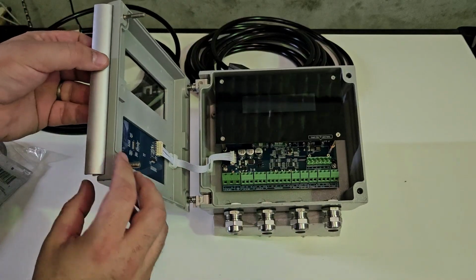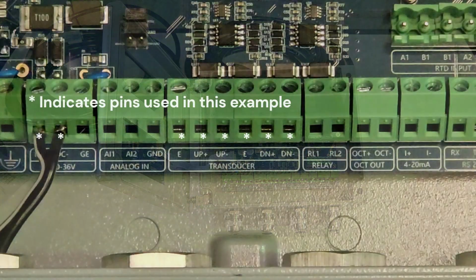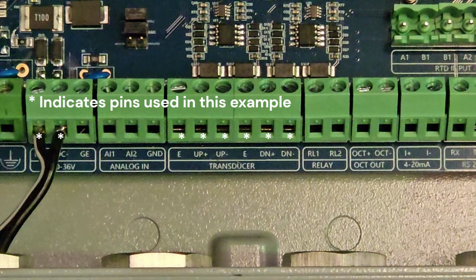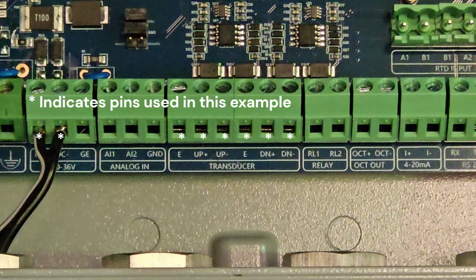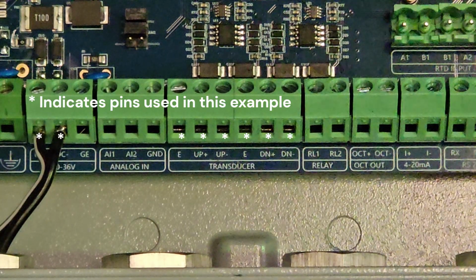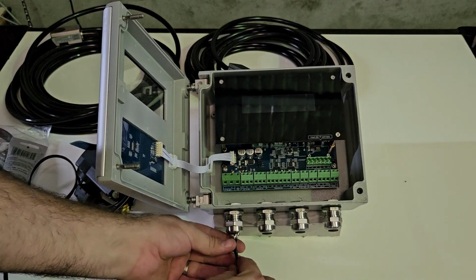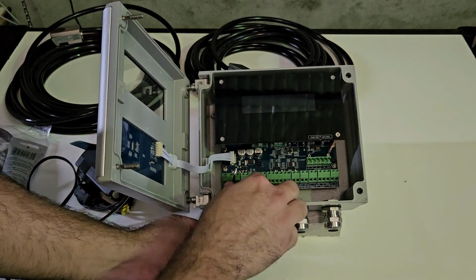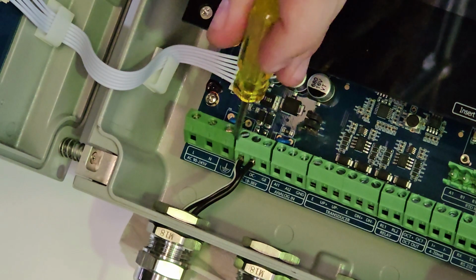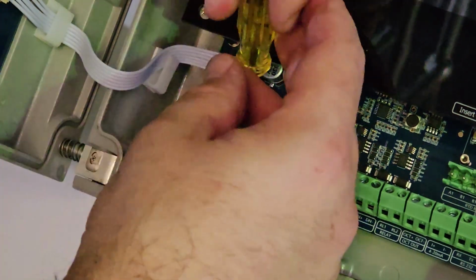Now you can connect the wiring. In this example, we will just connect a 12 volt DC power supply and the upstream and downstream sensor cables, but there are various other connections for various inputs and outputs which you can refer to the manual for more information on. First, loosen off all of the screws of the terminals which you will add wires into. Then feed the power supply wires through a cable gland. Insert the positive and negative power wires. Then tighten down the screws for those wires.